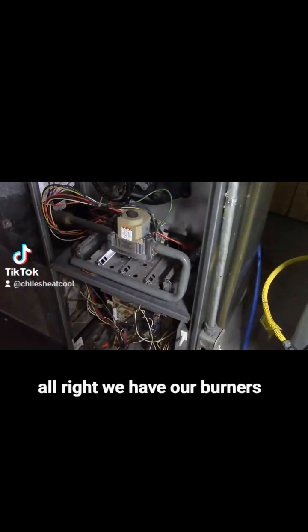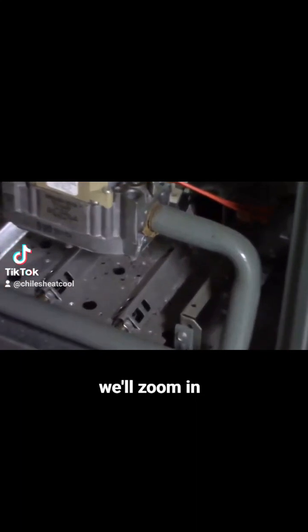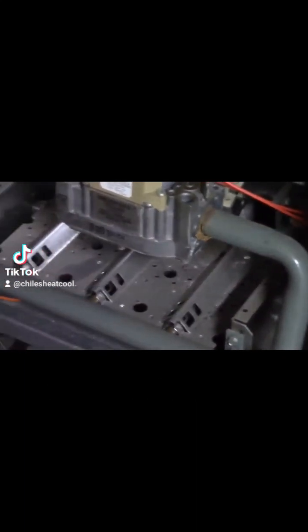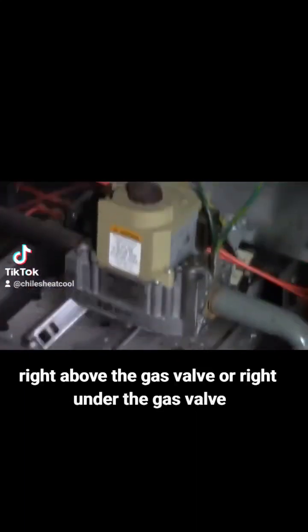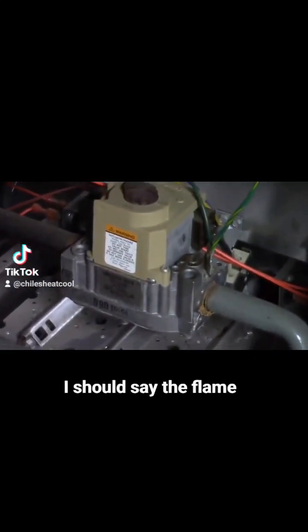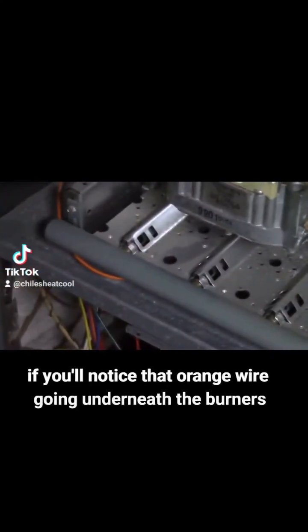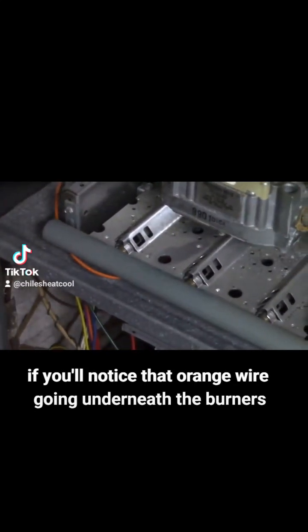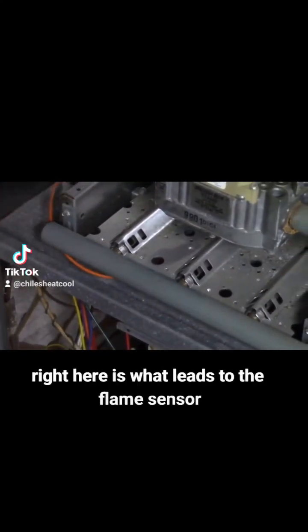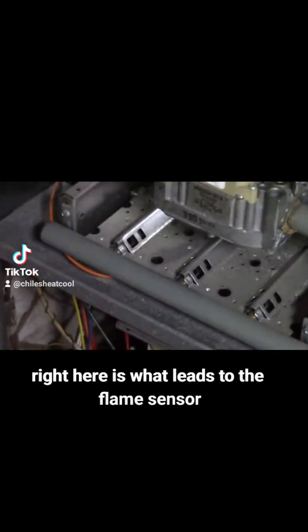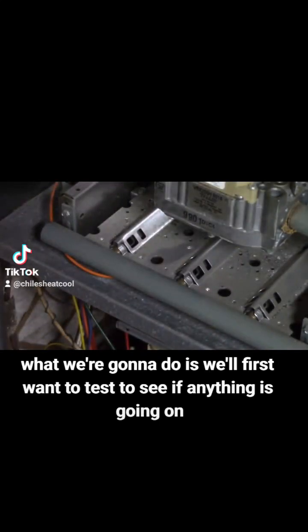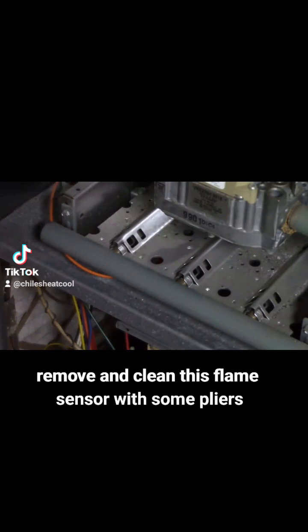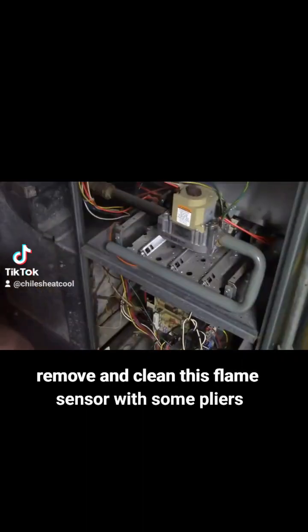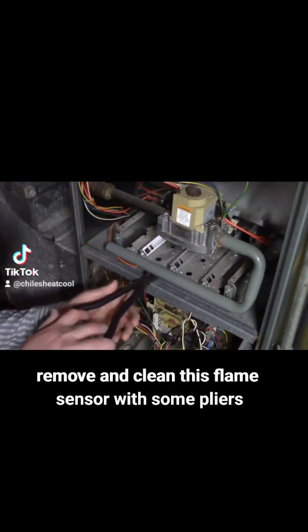Alright, we have our burners here. We'll zoom in. You see the plate that sits there right above the gas valve, or right under the gas valve I should say. The flame sensor, if you'll notice that orange wire going underneath the burners, right here is what leads to the flame sensor. What we're going to do is we'll first want to test to see if anything is going on. Then we'll proceed to remove and clean this flame sensor with some pliers here.